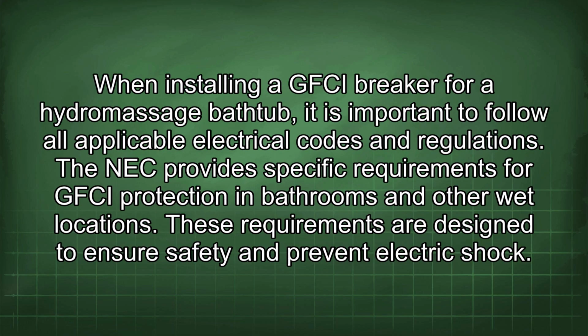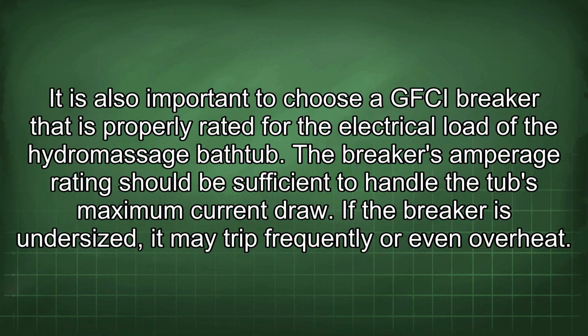When installing a GFCI breaker for a hydromassage bathtub, it is important to follow all applicable electrical codes and regulations. The NEC provides specific requirements for GFCI protection in bathrooms and other wet locations. These requirements are designed to ensure safety and prevent electric shock. It is also important to choose a GFCI breaker that is properly rated for the electrical load of the hydromassage bathtub. The breaker's amperage rating should be sufficient to handle the tub's maximum current draw. If the breaker is undersized, it may trip frequently or even overheat.